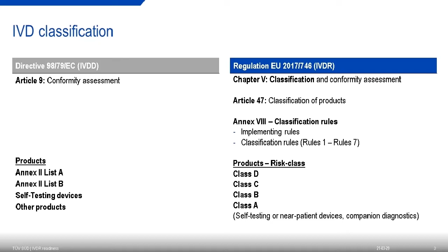It has 2 sets: implementing rules and classification rules, and that shows you how you have to understand and process your product. And you end up in one of the 4 new classes, going from A to D, from low risk to high risk. Self-tests will be found in B and C. Companion diagnostics will be found in C, and near patient tests could be found in B, C, or D, as they are basically classified in their own right and not specific to a class.